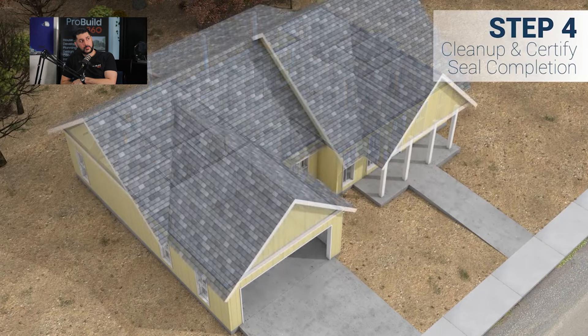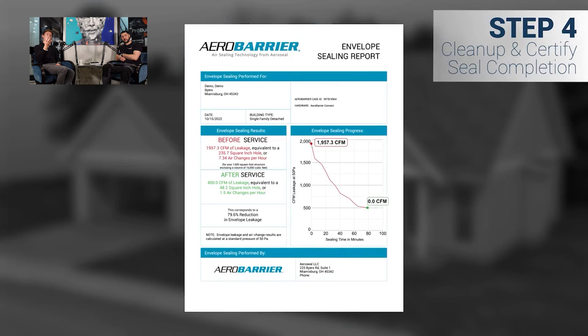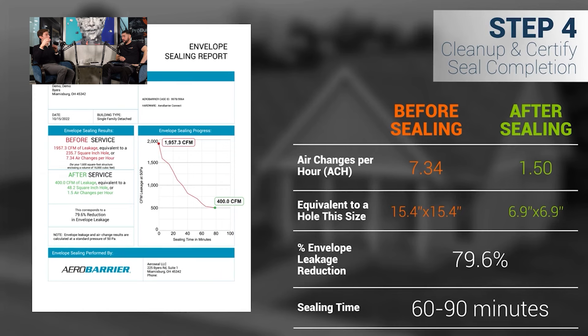In this build they've got ventilation systems in. A big question for builders is: how do I guarantee measurable, repeatable results? With new building regulations, you need to shoot the gap quite tightly between having uncontrolled or natural ventilation versus mechanical ventilation. We try to give builders a guaranteed result. No one really wants zero air changes per hour — is passive house zero? Passive house is 0.6.